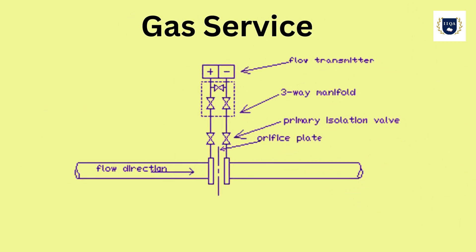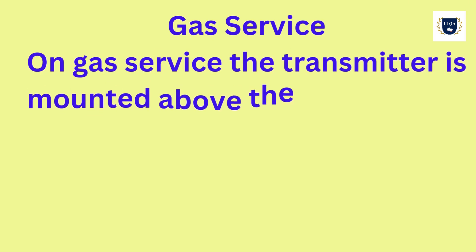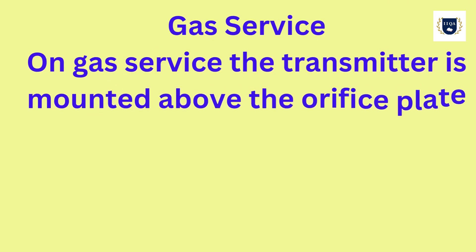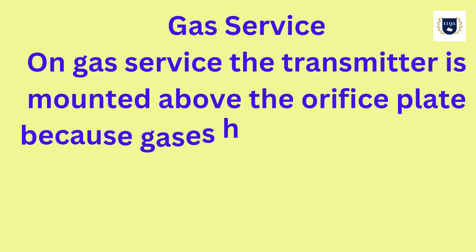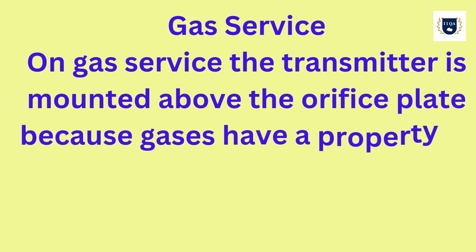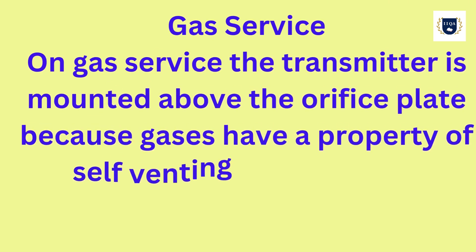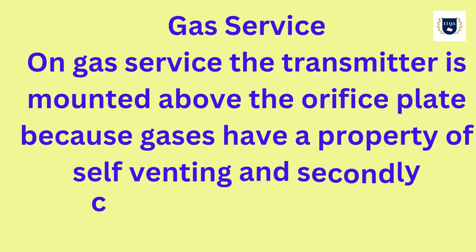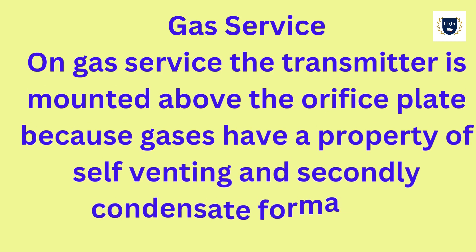Gas Service. On gas service, the transmitter is mounted above the orifice plate because gases have a property of self-venting, and secondly condensate formation.